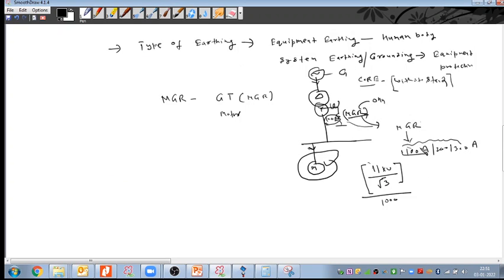For this current, there are two values. One is the maximum core withstand capacity based on the graph, or if that is not clear to us, then this value should not be more than the phase full load current of the generator or the full load current of the motor. Suppose 200 ampere is my full load current of the motor. I can say that yes, this motor can withstand 200 ampere. If 200 ampere fault current is flowing, it means the core will not be damaged. I can assume like this right now, Abhinav.